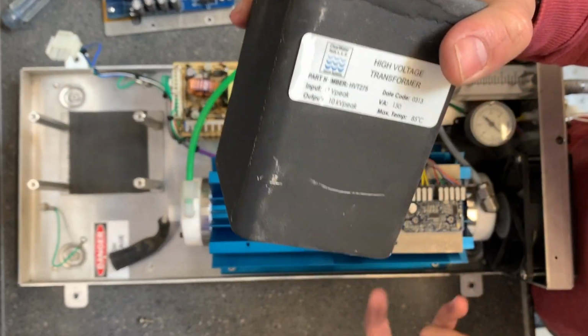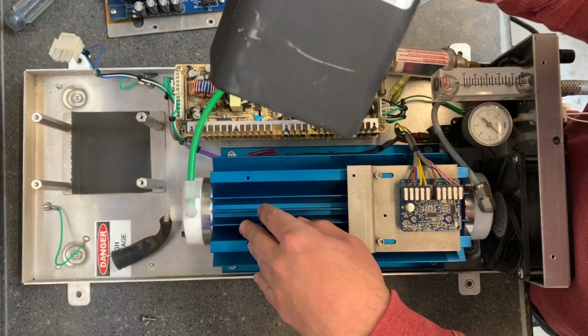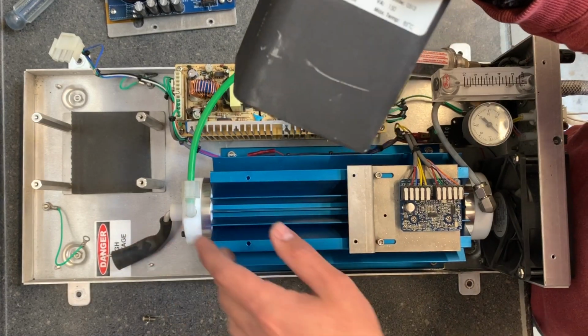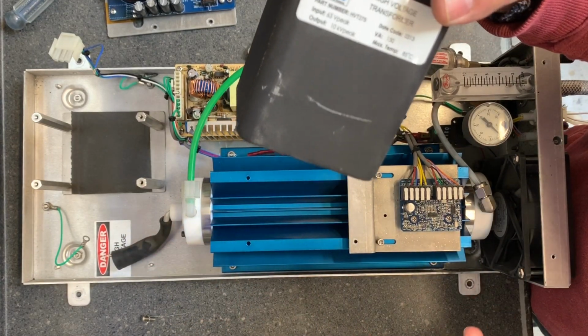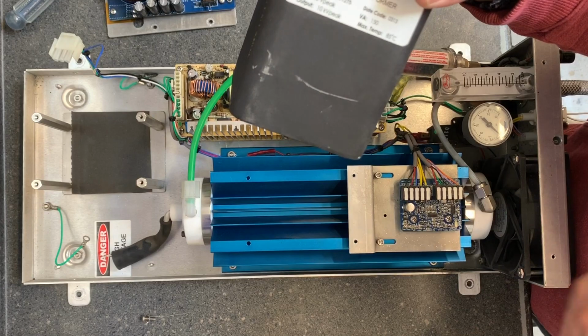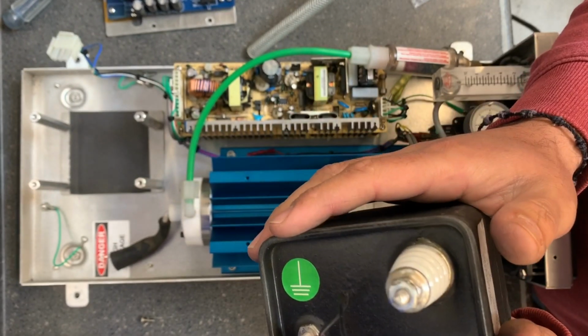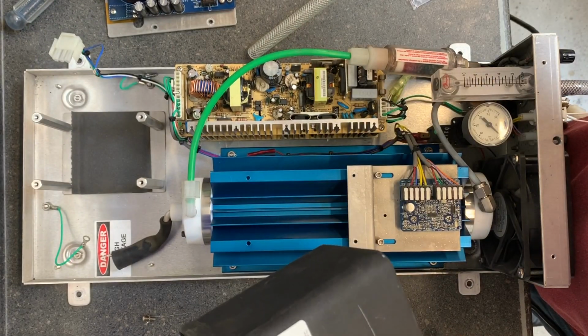But I still recommend you looking in, taking your chamber and doing the maintenance to it, which is pulling both end caps out. Make sure you don't have broken glass, or if it's dirty, clean it out, and I'll show you how to do that in the next step. So this is clearly a bad transformer. This is why we're getting the fault light most likely. And I'll show you how to rebuild the chamber next.